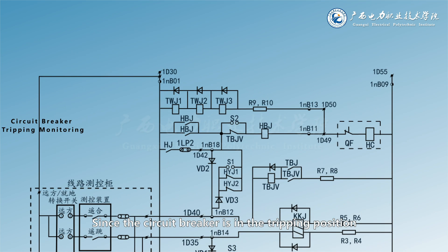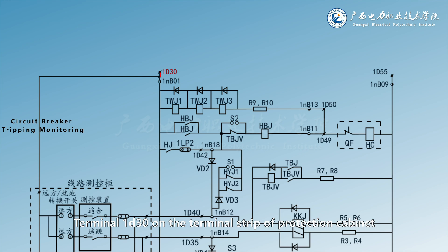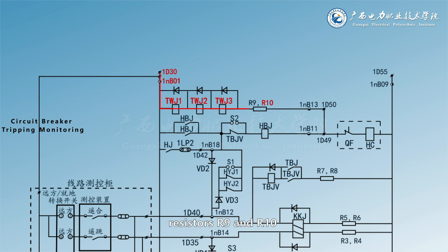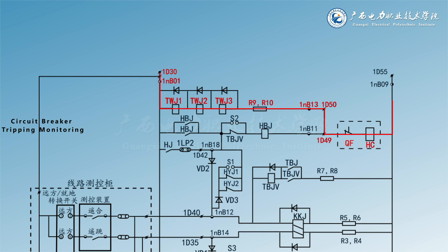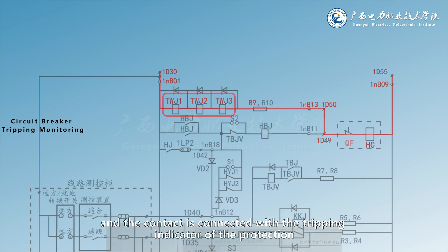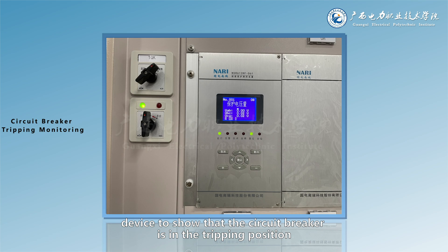Since the circuit breaker is in the tripping position, its auxiliary contacts are closed, forming the following electrical paths: 1D30, 1NB01, TWJ1, TWJ2, TWJ3, R9 and R10, 1NB13, 1D50 and 1D49, QF, HC, 1NB09, 1D55. Therefore, the coils of TWJ1, TWJ2 and TWJ3 is excited, and the contact is connected with the tripping indicator of the protection device to show that the circuit breaker is in the tripping position.